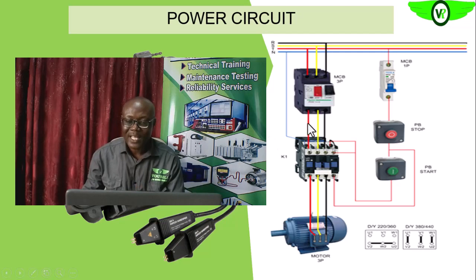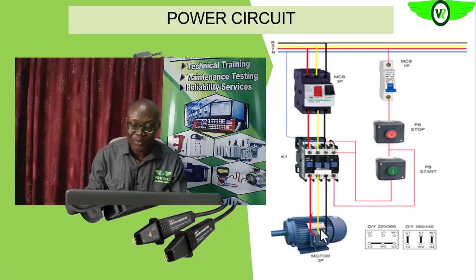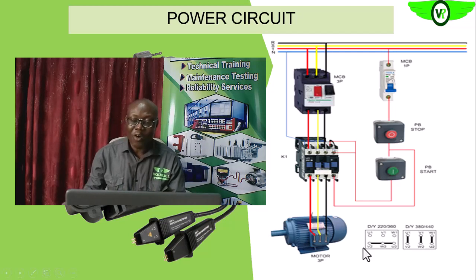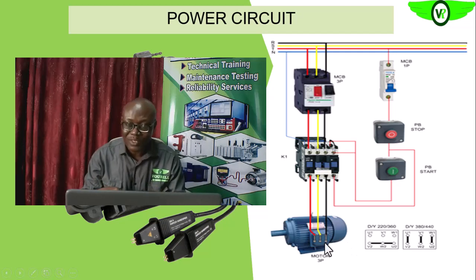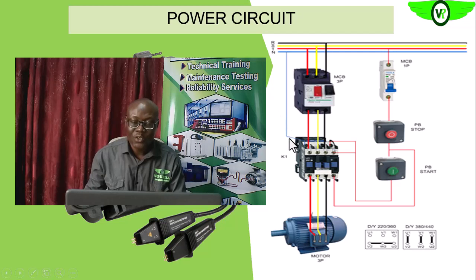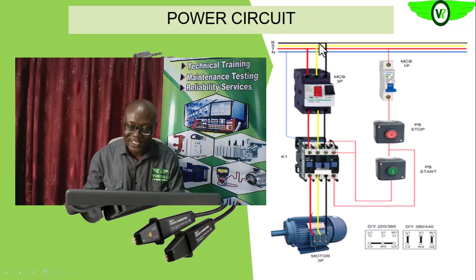it means that something is wrong, okay, and that could mean that either any of these lines, they have high resistance connections, or within the electric motor itself, the windings may be shorted, or it has high resistance connection at their various connection points, either at the terminal block or within the windings where we solder the coils or the windings together. That could be the reason why we have this unbalance. So you need to check to ascertain which area in the circuitry is actually causing this unbalance.